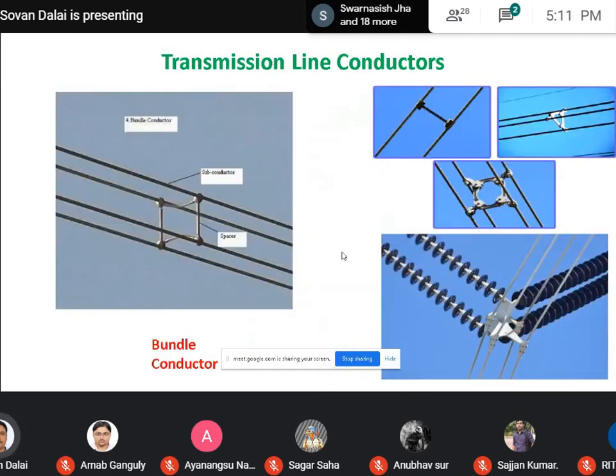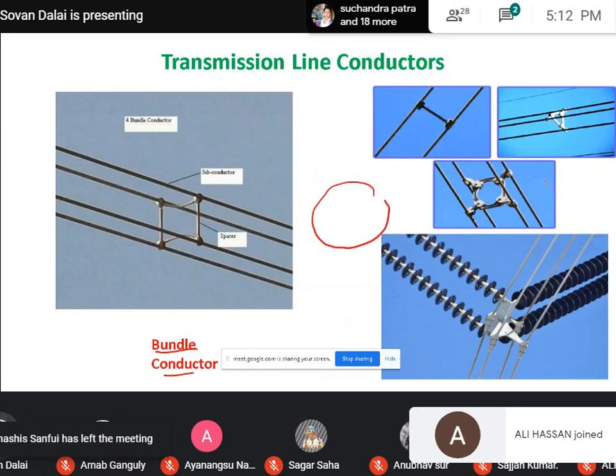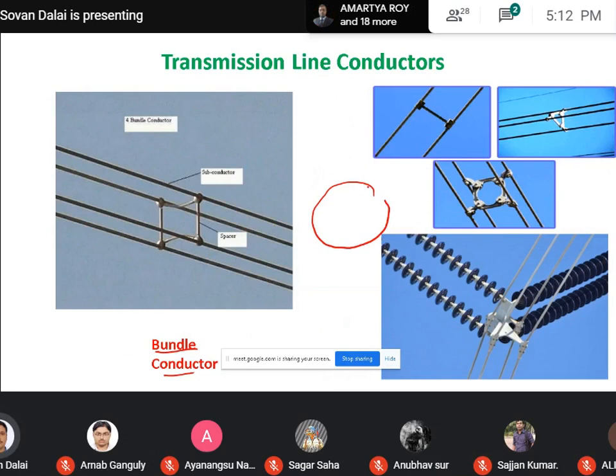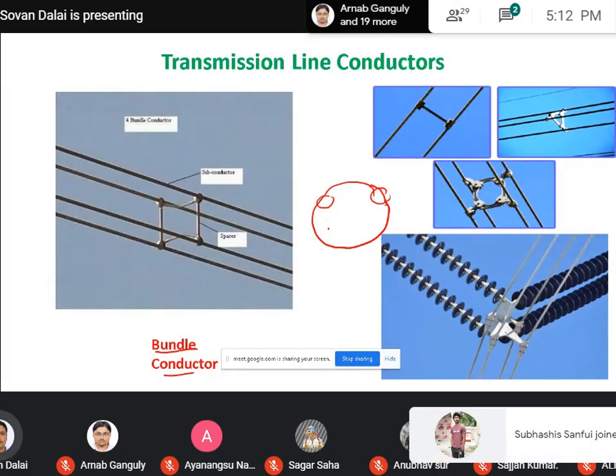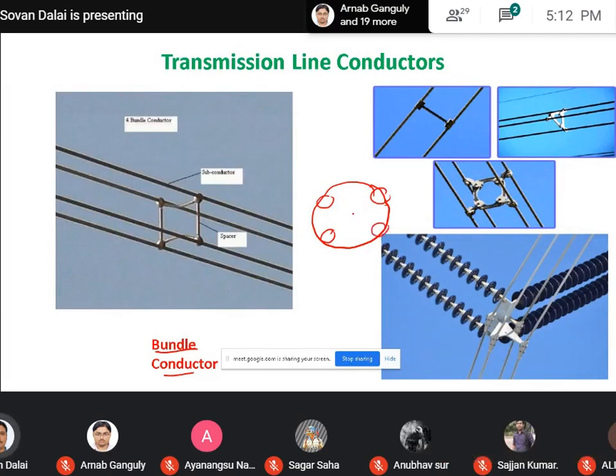This type of conductor is generally used in the transmission line. But another type of conductor also used in the transmission line is called the bundle conductor. What is a bundle conductor? A bundle conductor also consists of a number of subconductors, but instead of filling the whole diameter with subconductors, it consists of say 4 conductors. Sometimes it may consist of 5 conductors, sometimes 6, but most of the portion of this conductor is basically empty or hollow.